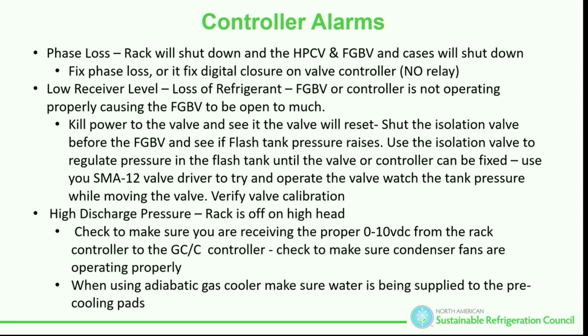But we've got to make sure the controllers are working. Make sure I'm getting that 0 to 10. Make sure somebody didn't pull it. My fans are running either way, depending on if I set it up 0 to 10 or 10 to 0. Know which way I set it up. Could be that different guys set them up. Could be the flash tank is reading a higher pressure, reading an alarm set point, which is shutting down the HPV. Could be tripping off on high pressure on the vessel. So these are all things I have to investigate when I'm looking at that, right? Is that what you just said?